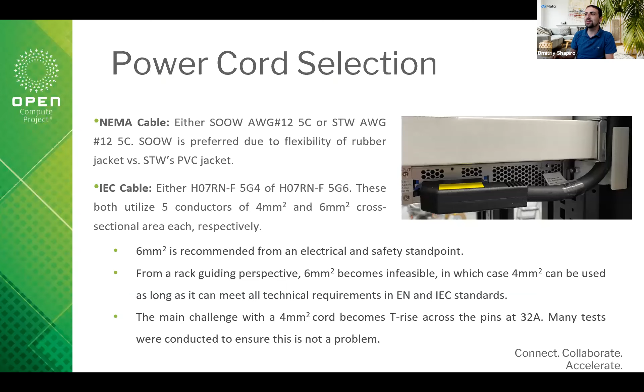As Will mentioned earlier, the problem with that becomes the T-rise across the pins at 32 amps, so we had to do a lot of tests to ensure this wasn't a problem. We did redesigns within the power shelf, using thicker wire on the power shelf side connector, and making that a crimp connector instead of PCB mounted. Because of that, our T-rise was significantly below 30C, so we achieved a solid design.